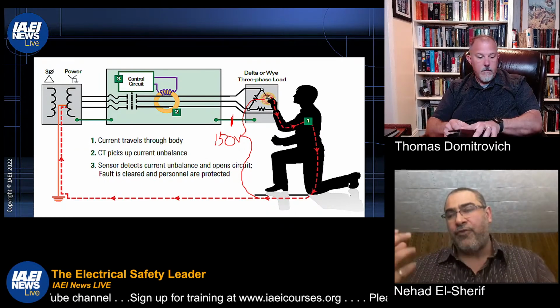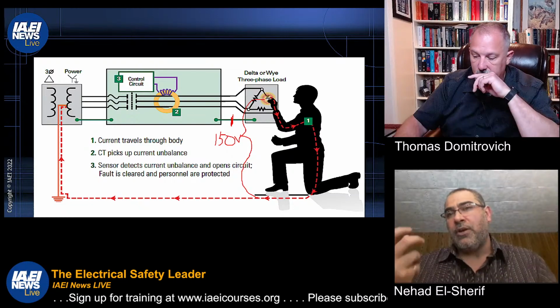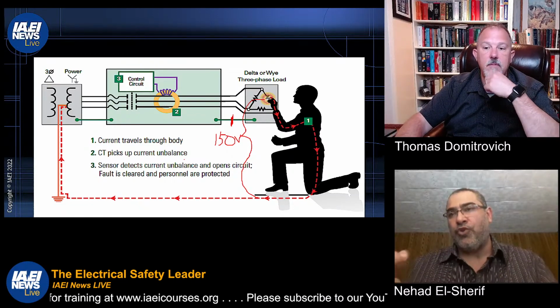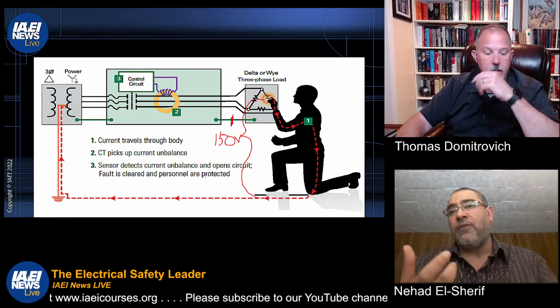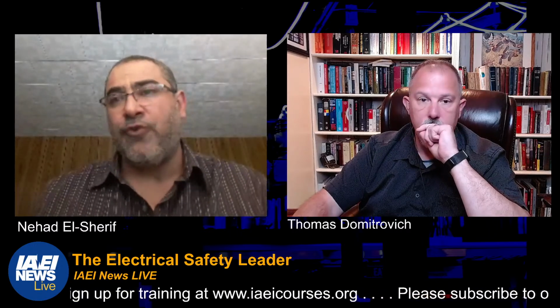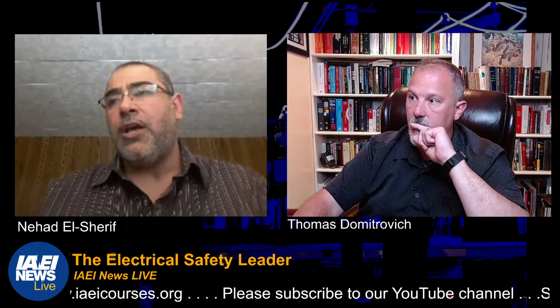So the idea for the special purpose GFCIs to monitor the equipment grounded conductor is to make sure that we don't get into a condition where the majority of the ground current will go to the person. Ideally, preferably all the current would go through the equipment grounded conductor back to the source. But it's a current divider circuit. You have two impedances, the person in touch with the piece of faulty equipment and the equipment grounded conductor of that equipment. So we need to make sure that the equipment grounded conductor impedance is low enough, as designed, so that the majority of this current bypasses the person and goes through the equipment grounded conductor back to the source, protecting the person.